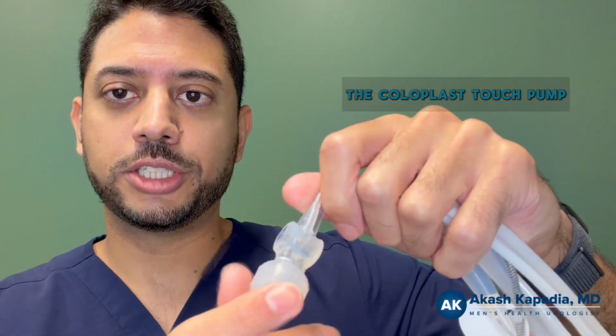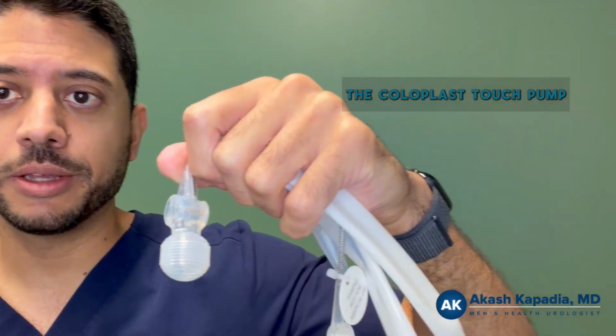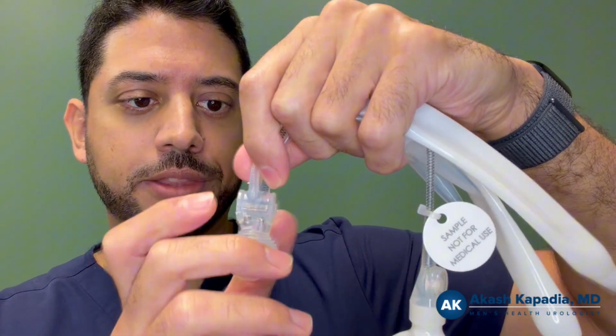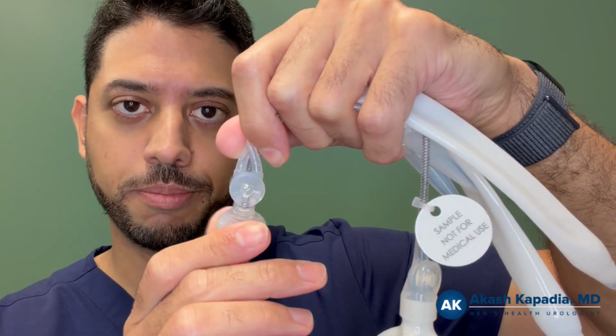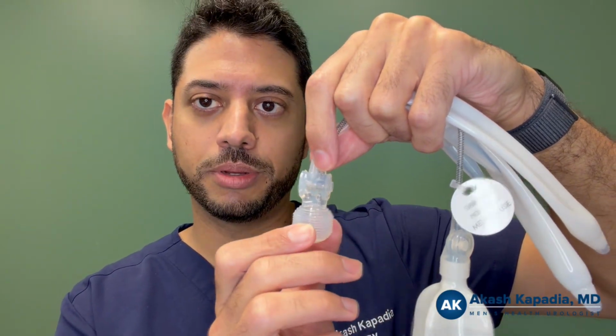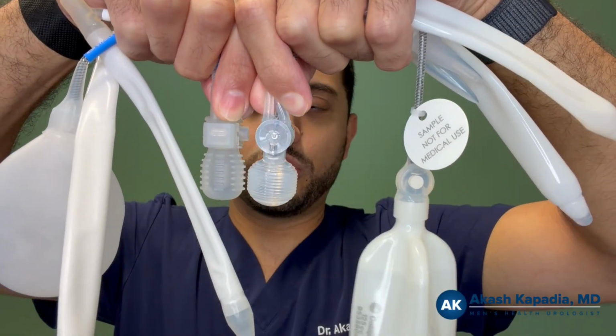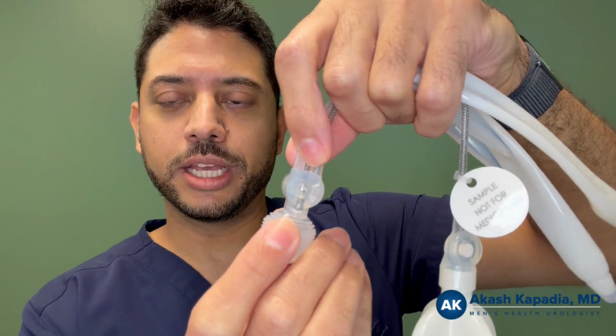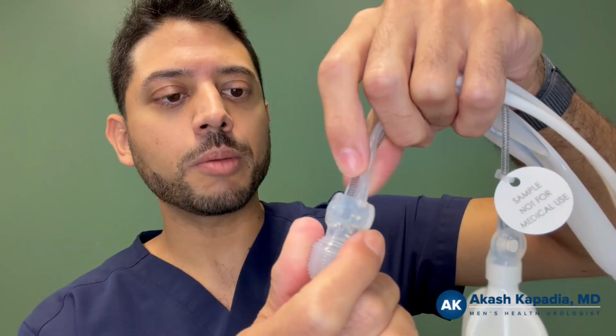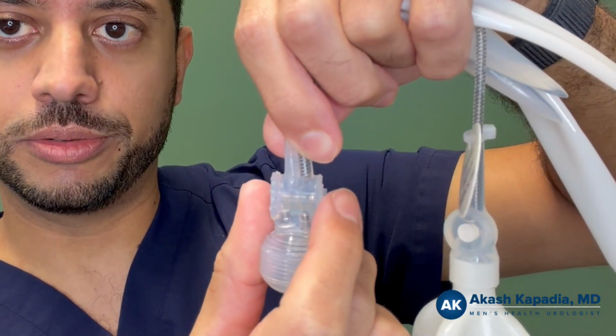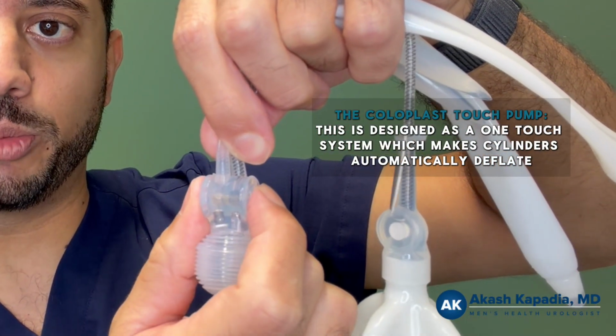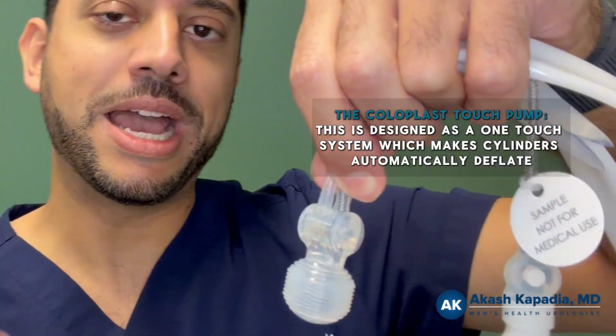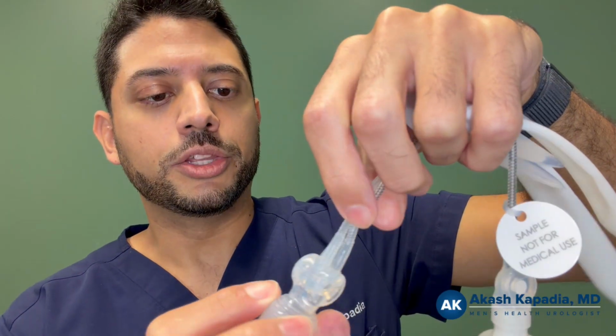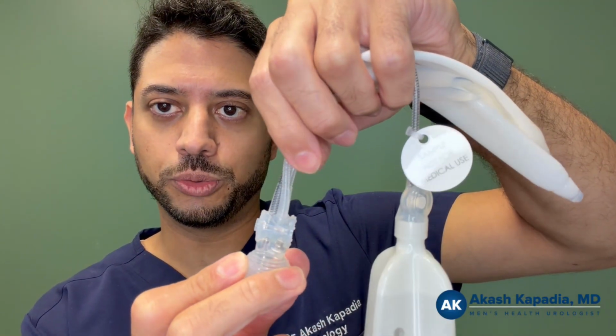Now, pump number two is the One-Touch pump designed by Coloplast. This is meant to compete with the AMS Touch pump by Boston Scientific. In design, you can tell right away that this device is a little girthier compared to the Genesis at the shoulder of the pump. In fact, it matches the width of the pump quite similarly to the Boston Scientific, and in length it's also very similar. It has a nice wide inflate, identical to the Genesis pump, but now we've introduced this button for the deflate. This is designed to be one touch, meaning you press and the cylinders automatically deflate, matching the technology of the AMS Touch pump. The tubing now changes—it's not in line, more similar to the Boston Scientific tubing.